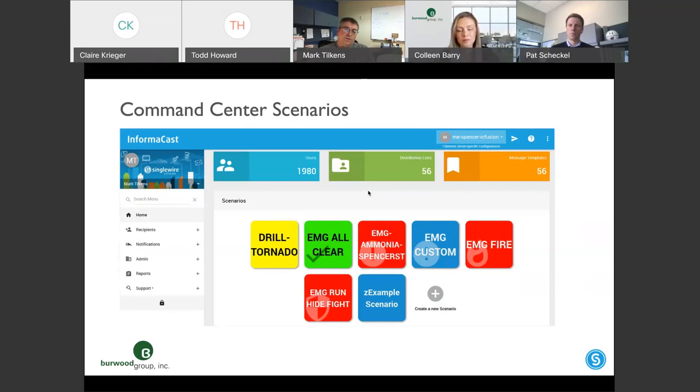in the Appleton area is going to receive an email and an SMS text when there's a fire happening at one of our 9 buildings here in Appleton. So to put automation behind that, people were a little hesitant, but after they learned how the tornado one happened, our facility and safety people came back at me and said, this is a must. It's good to have a manual method to initiate a fire, but let's take the manual element out of it. And so we've tied in all our panels with contact closures, and it automatically happens.